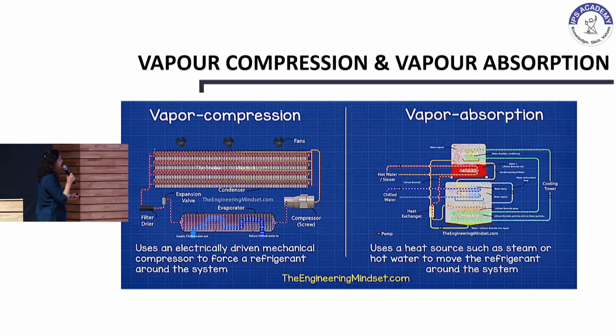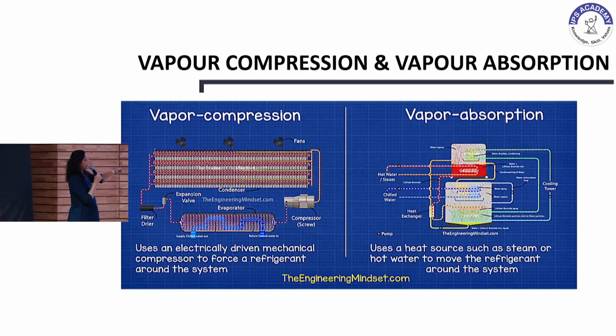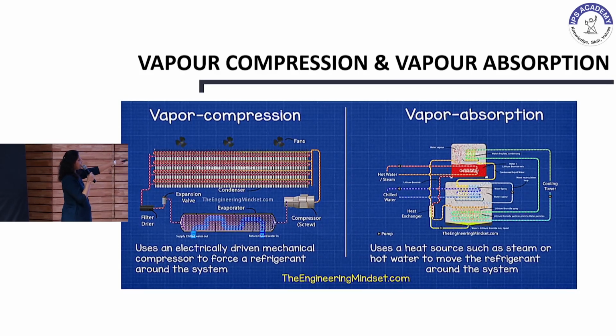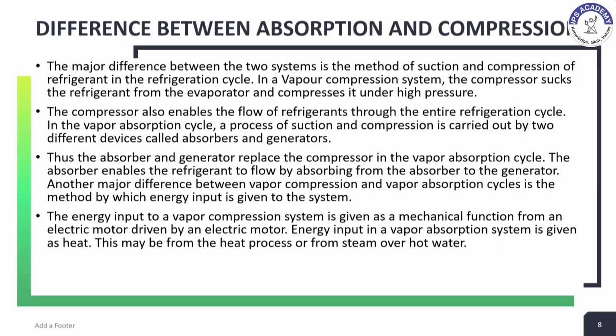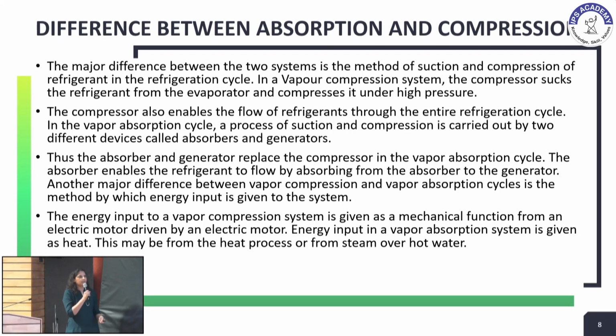In vapor absorption, you see that the compressor is missing. So you have a generator and an absorber, with all the other components kept the same. What is the major difference between an absorption and a compression cycle? The major difference between the two systems is the method of suction and compression of the refrigerant in the refrigeration cycle. In a vapor compression system, the compressor sucks the refrigerant from the evaporator and compresses it under high pressure. In a vapor absorption system, the process of suction and compression is carried out by two different devices, called the absorber and the generator.